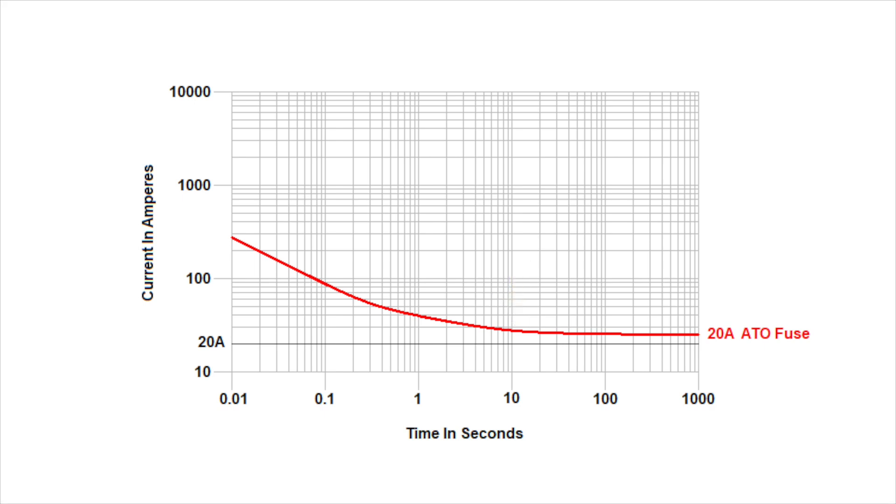And as the overcurrent increases, the time to blow becomes less. For example, on the left side of the chart, a 20 amp fuse can withstand almost 300 amps for up to 10 milliseconds before blowing.